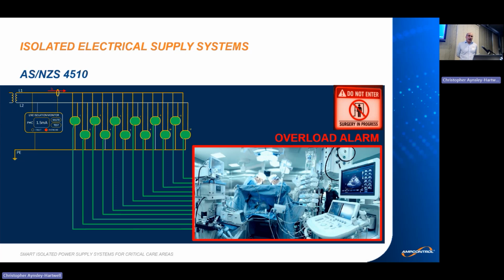A similar scenario happens when the line isolation monitor triggers an overload alarm. What it means is that the isolation transformer is overloaded. But again, the line isolation monitor doesn't tell us which piece of medical equipment is responsible for the excessive current. And it's up to medical personnel again to figure out which particular piece of medical equipment is responsible for the excessive current.